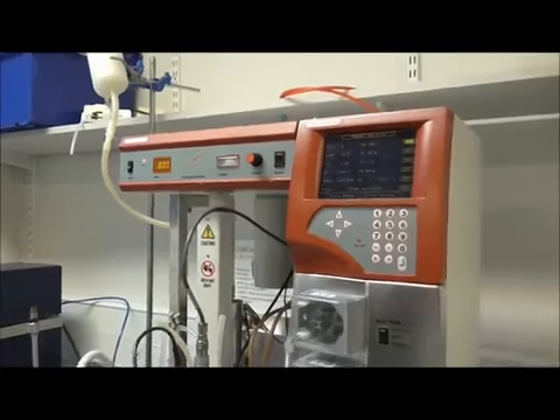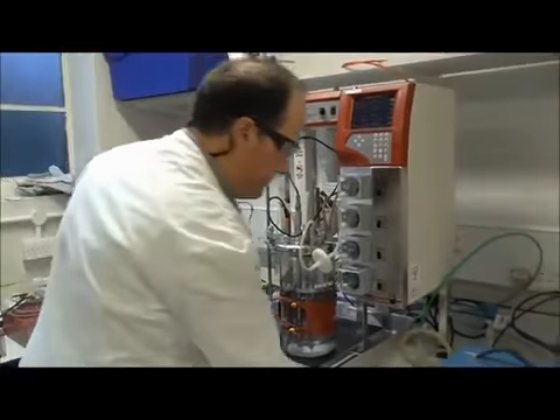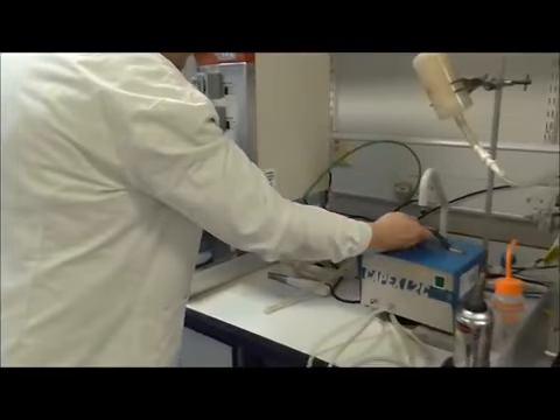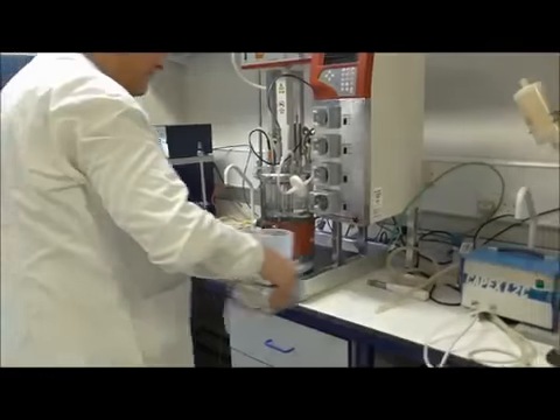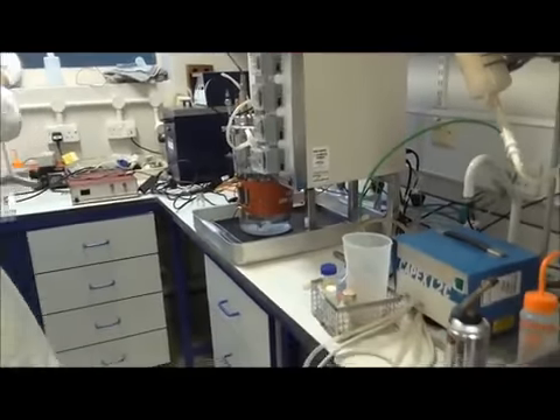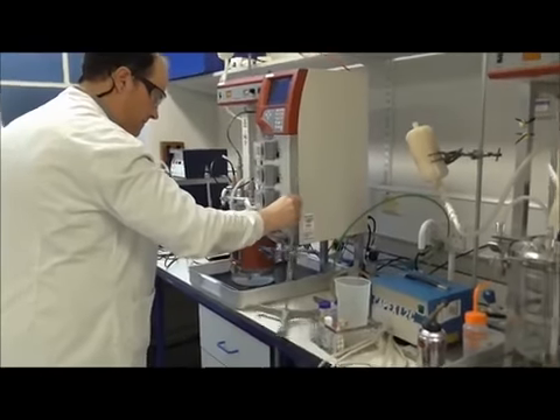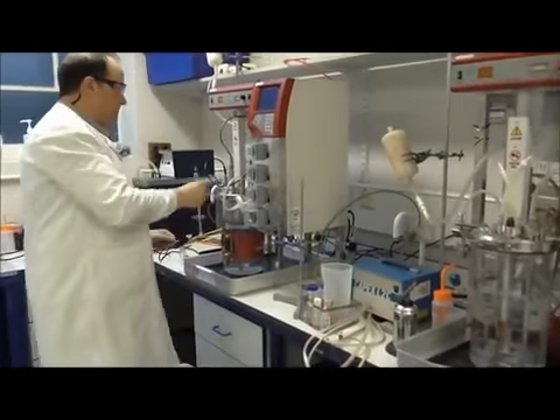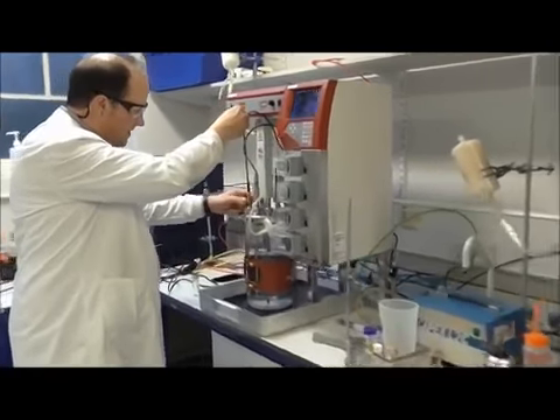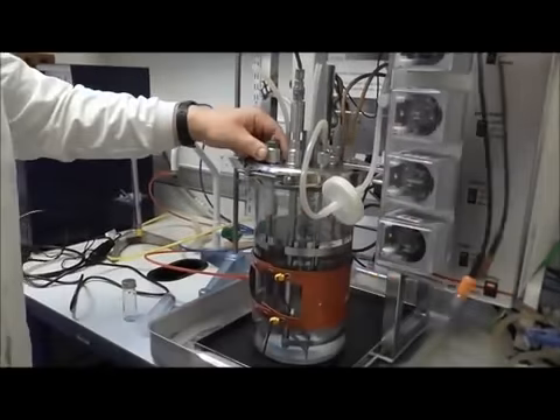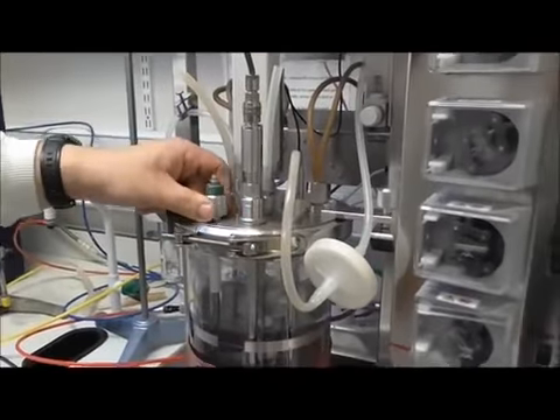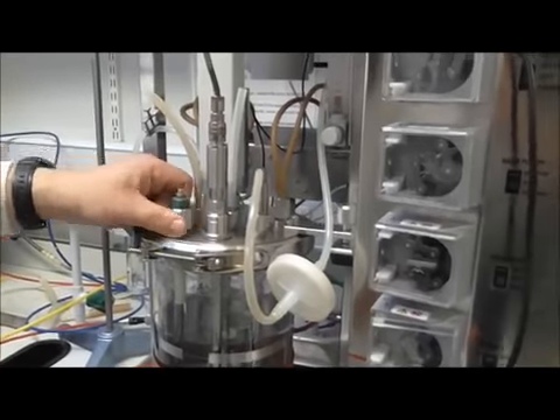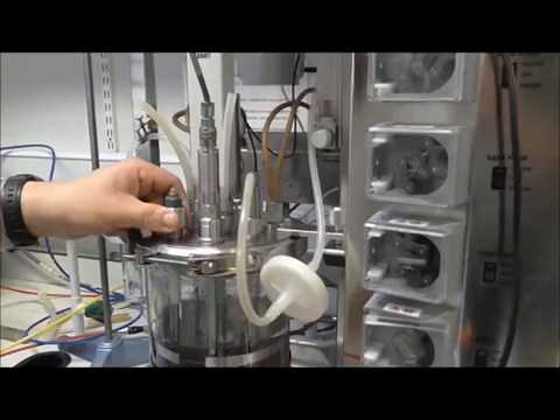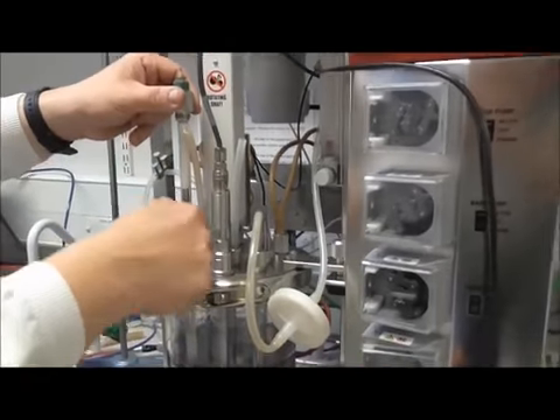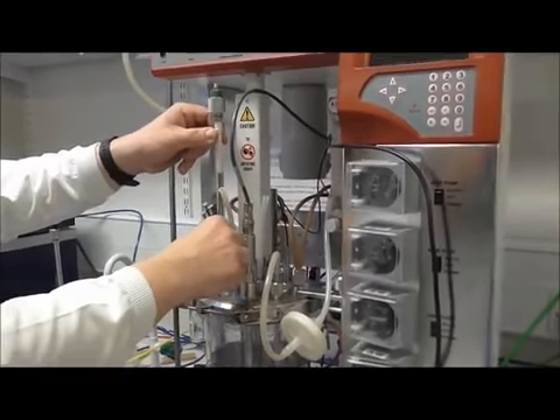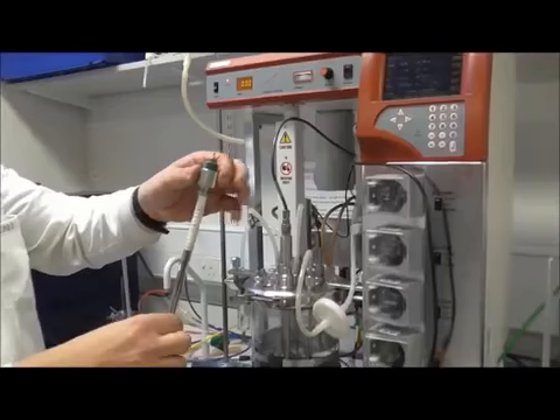Right, on to probe calibration. We'll start off with the pH. We need to get a few bits and pieces together. So we disconnect the lead, and these are normally held in finger tight, so just unscrew the probe and then very carefully pull it up from the top plate. There is an O-ring that sits in here, so there is a little bit of resistance, and just carefully withdraw it, and there we are.